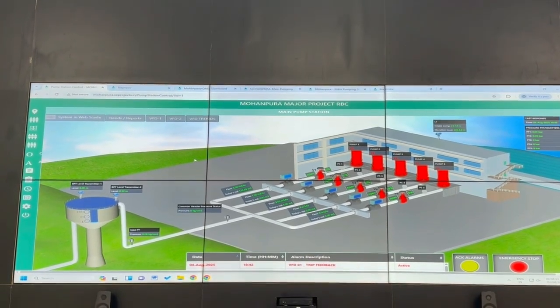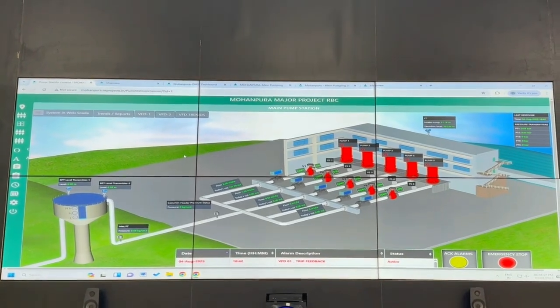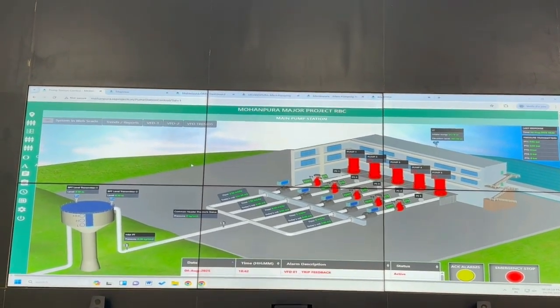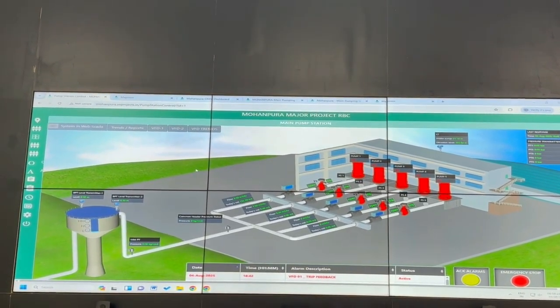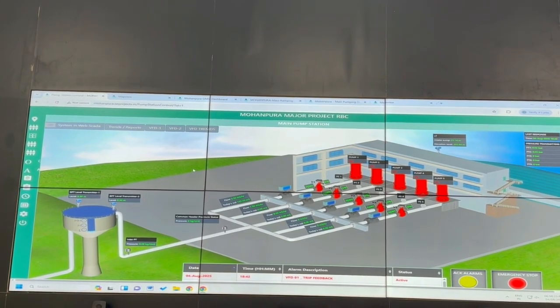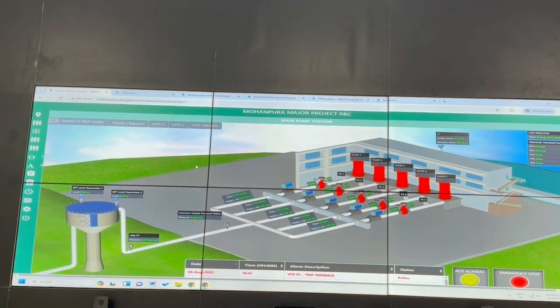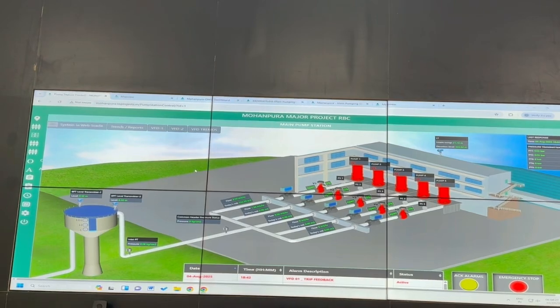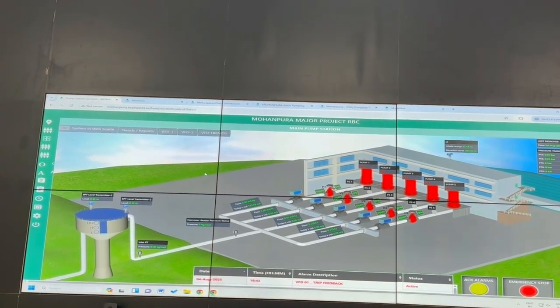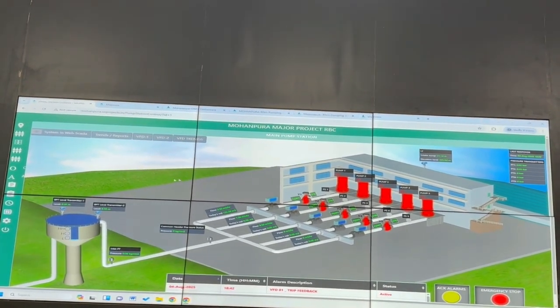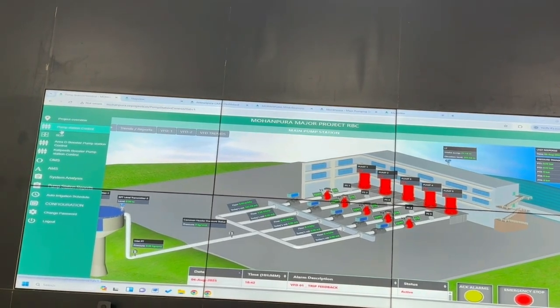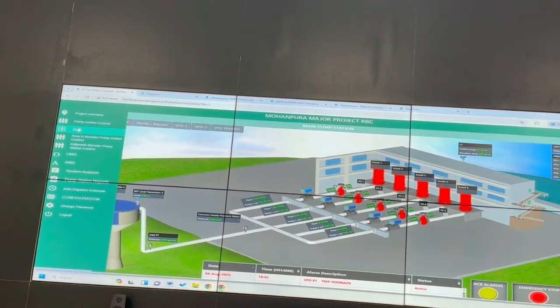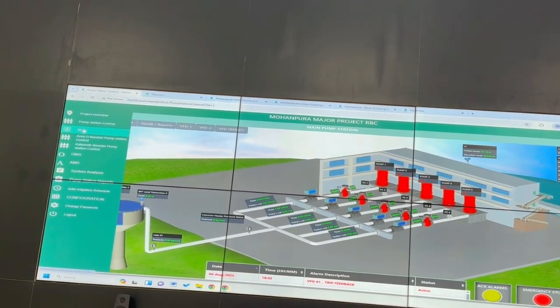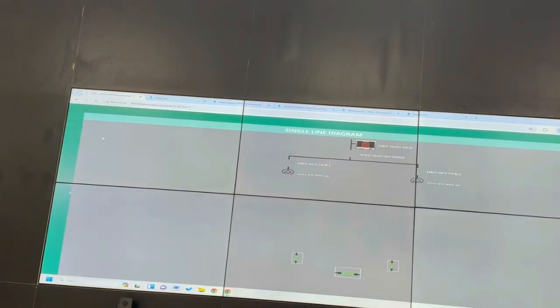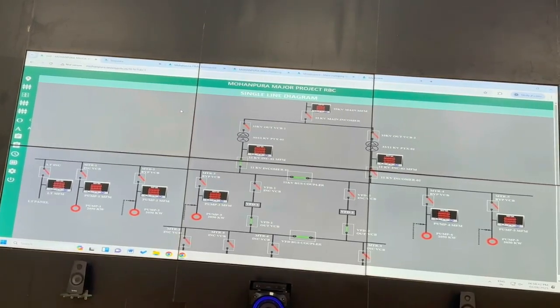The rising pipe you can see in the picture, the rising pipe is taken to the water tank. The water tank was there in the video before. It helps in creating the pressure for the low lying area. So the water goes in pressure. Two level transmitters are installed on the tank because it's a critical point. Wherever there is a critical point, there is extra equipment fitted.